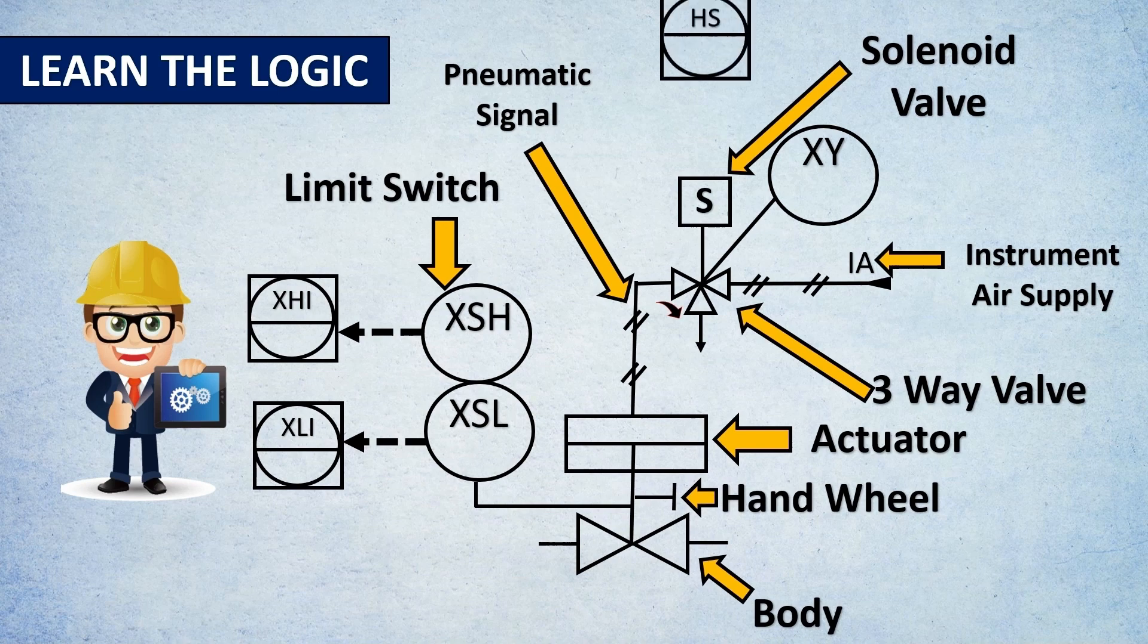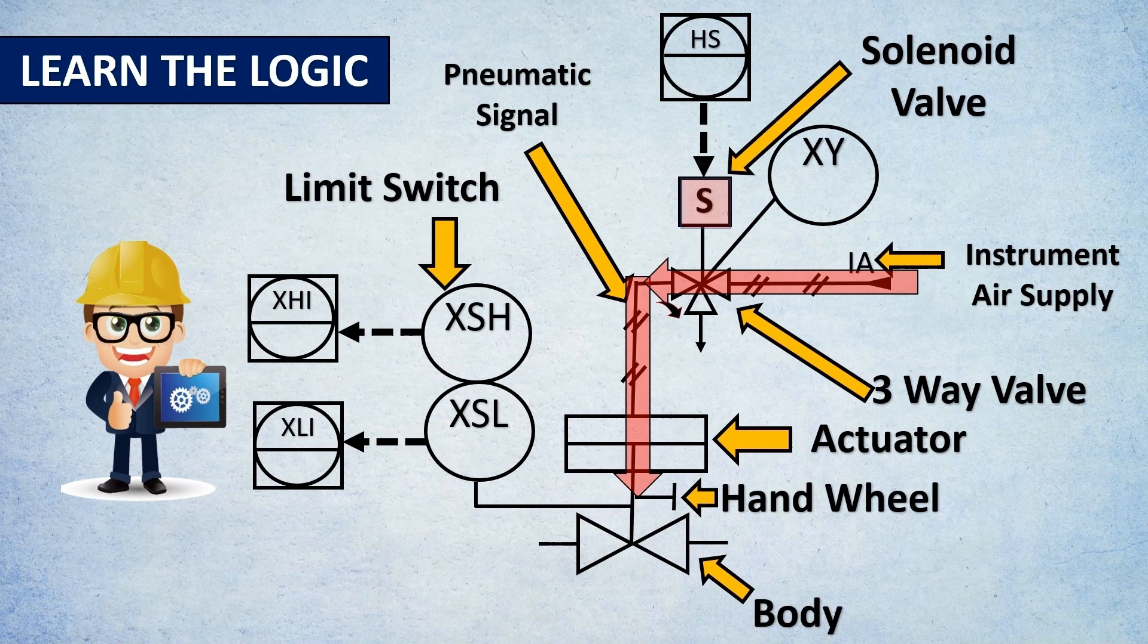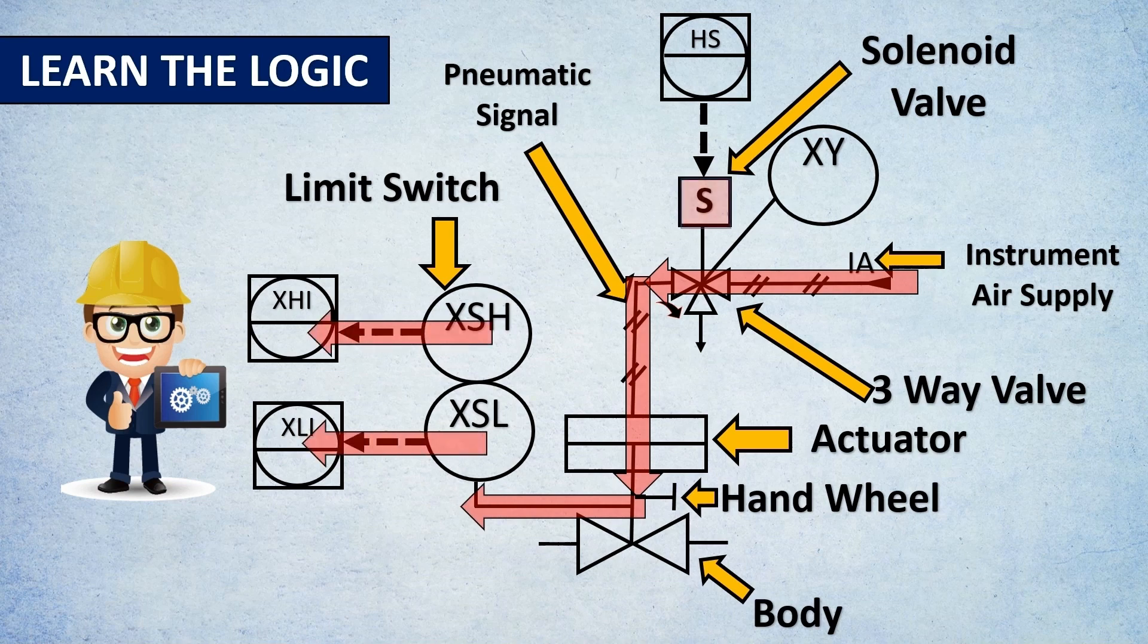The limit switch is there. When the operator presses the hand switch, the solenoid becomes active. Once the solenoid is active, the instrument air supply goes to your actuator, which actuates the valve. For our example, let's say it opens the valve. Then the limit switches show the operator that the valve has opened.